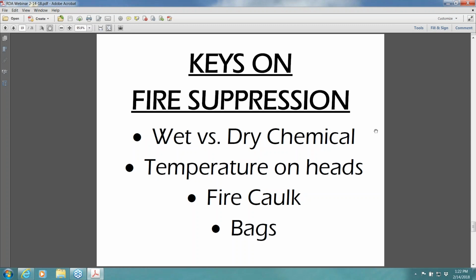So what we always advise is that your fire suppression specialist puts in a head that is rated above 200 degrees, typically 250, that type of thing. If you've got a fire, it's going to get that hot, it's going to go off. So no reason to have a premature discharge on your fire suppression just from the operation of the paint booth. And everywhere that fire suppression penetrates the booth, that area needs to be fire rated caulked, so that is a seal that is appropriate for that system.